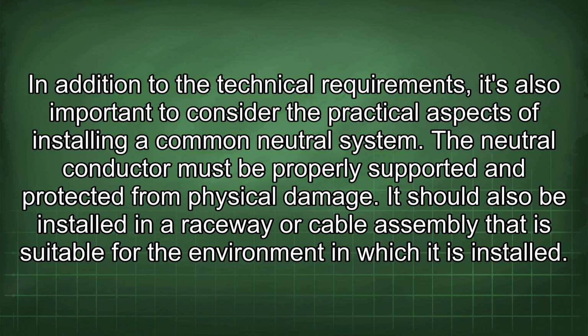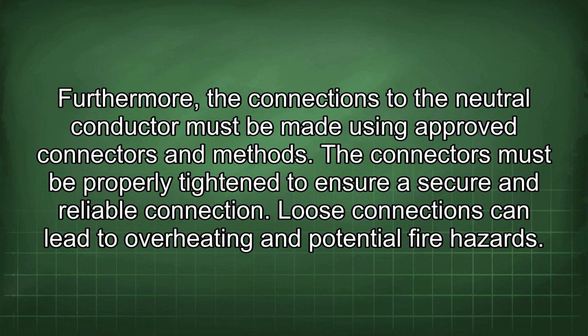In addition to the technical requirements, it's also important to consider the practical aspects of installing a common neutral system. The neutral conductor must be properly supported and protected from physical damage. It should also be installed in a raceway or cable assembly that is suitable for the environment in which it is installed. Furthermore, the connections to the neutral conductor must be made using approved connectors and methods. The connectors must be properly tightened to ensure a secure and reliable connection. Loose connections can lead to overheating and potential fire hazards.